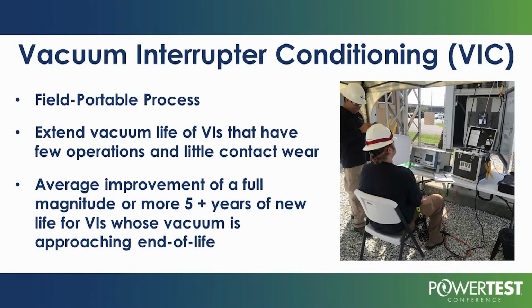So with vacuum interrupter conditioning, we're basically trying to build 2 processes. A shop process by which we can condition every interrupter that comes through ours or anybody's breaker shop or through your shop. And we're trying to build a field system where this can be applied in the field easily, where you can condition the interrupters as part of your normal maintenance program. When you typically go in and maintain a breaker, you do a standard battery of electrical tests. VI conditioning should be inserted right in that spot to where it's constantly conditioned, where the pressure is constantly kept as low as possible. And we're going to explain how that works here.